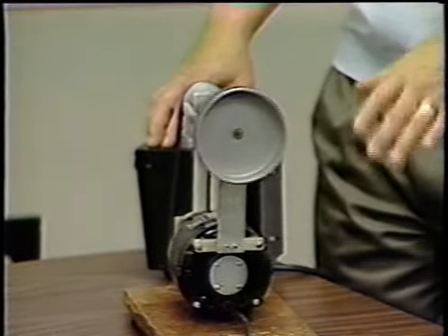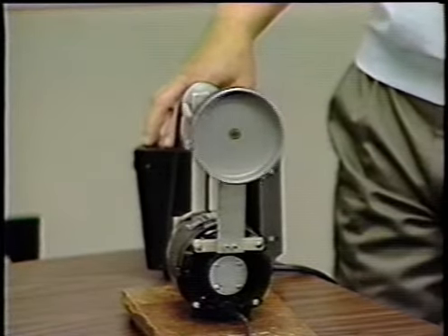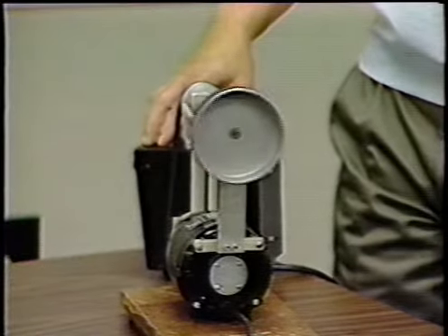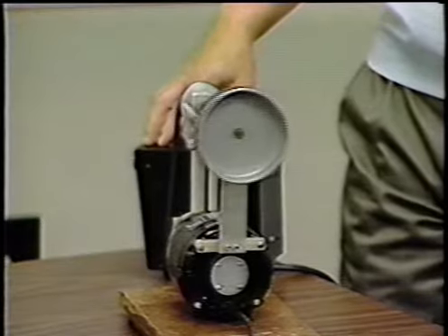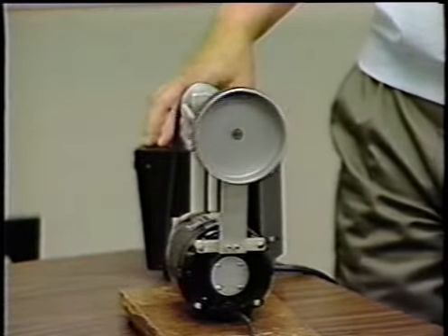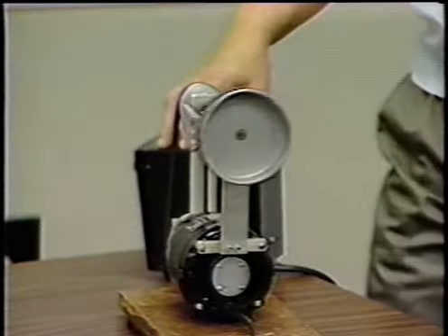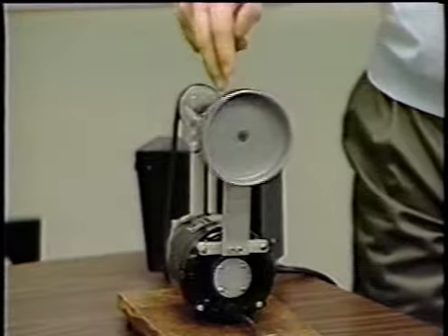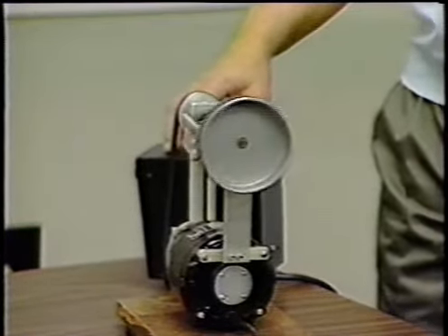Again, this is resonance. One of the things that you'll note, this is a structural resonance, and note that the vibration is extremely directional. It's almost entirely horizontal. And this is one of the things that we look for in doing a vibration analysis to get indications of possible resonance problems. Right here, we're probably looking at almost a quarter of an inch peak-to-peak motion in the horizontal direction. Relative to that, in the vertical and the axial directions, you have very, very little vibration.